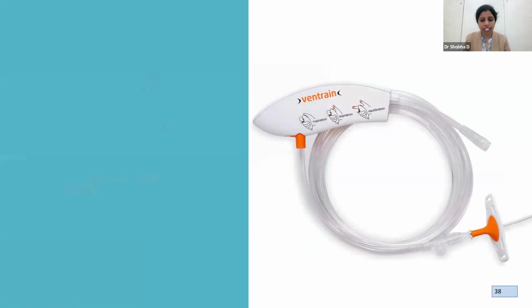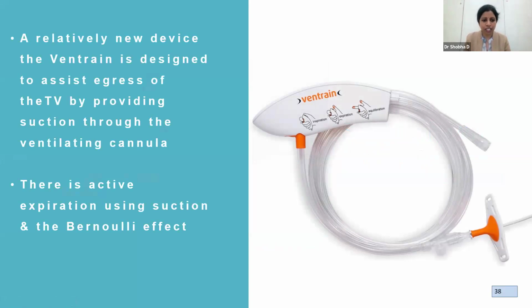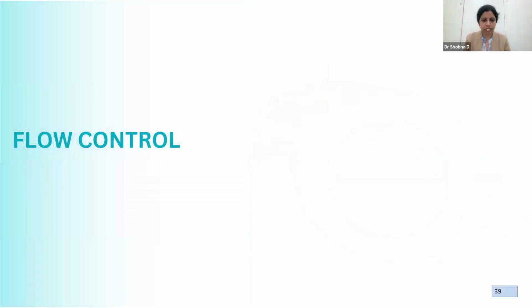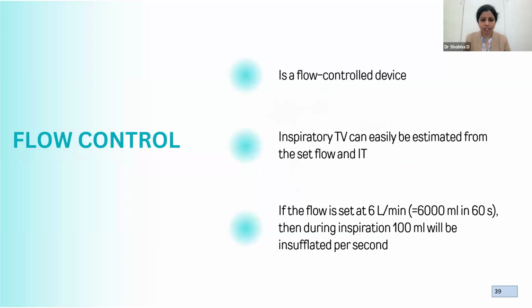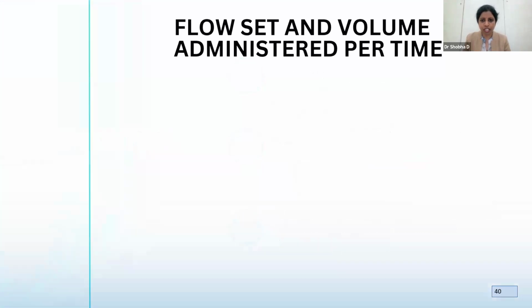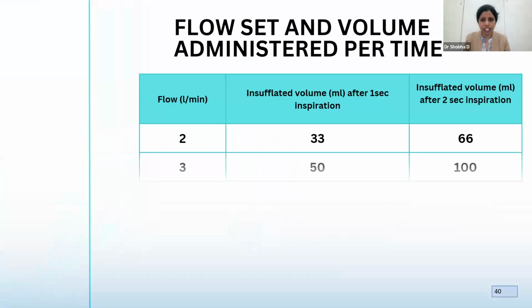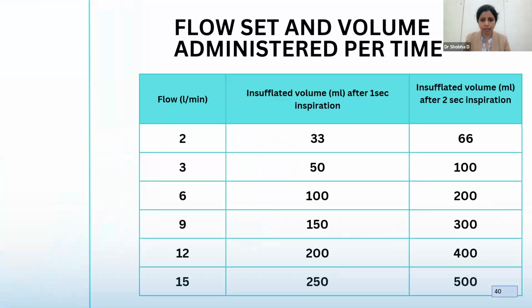So all these were basically passive expiration, which had chances of barotrauma. One of the latest, relatively new devices is the Ventrain, where there is active expiration using suction and the Bernoulli effect. It is a flow control device where the inspired tidal volume can easily be estimated from the set flow and the inspiratory time. So if the flow is set at 6 liters per minute, for example, inspiration will be around 100 ml in a second. So this is a flow chart, a table which shows the flow and the volume that's administered per time.